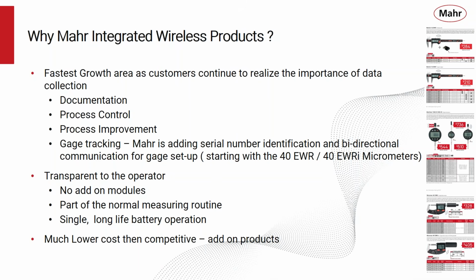Mahr is adding a new serial number identification feature with bidirectional communication for gauge setup, which now allows you to not only record the measured value, but also record the gauge that was used to measure with. So now for critical operations where you want to make sure everything is calibrated and you have the right data, we can give you both the gauge number and the measurement with the string of data.